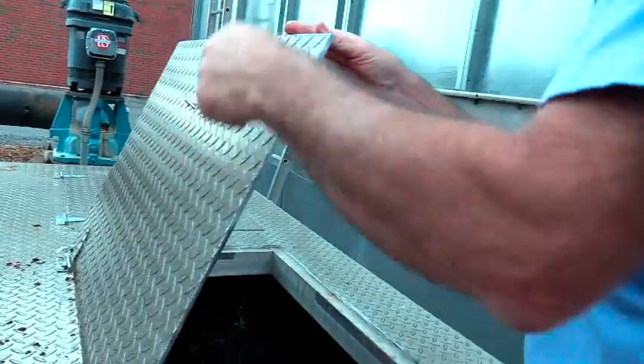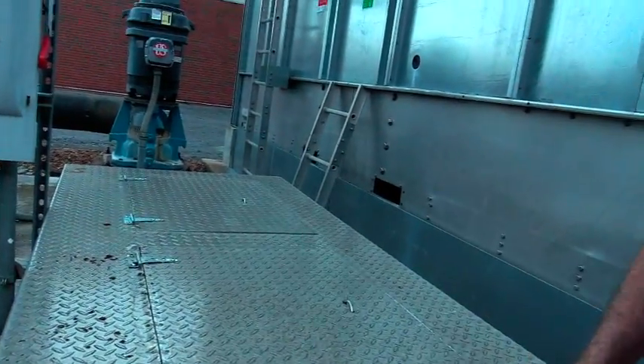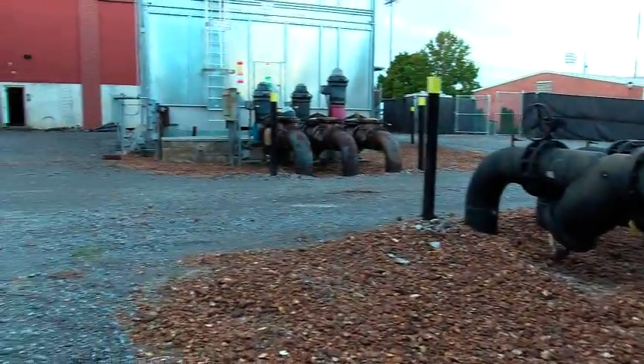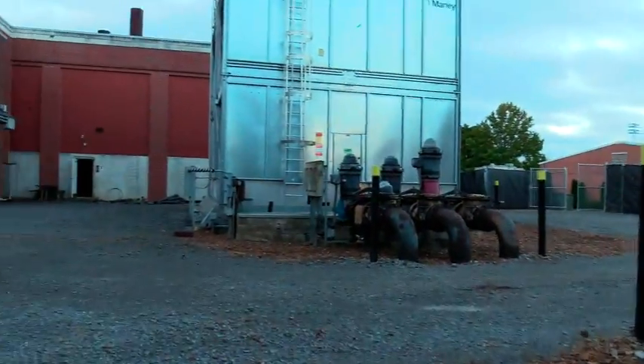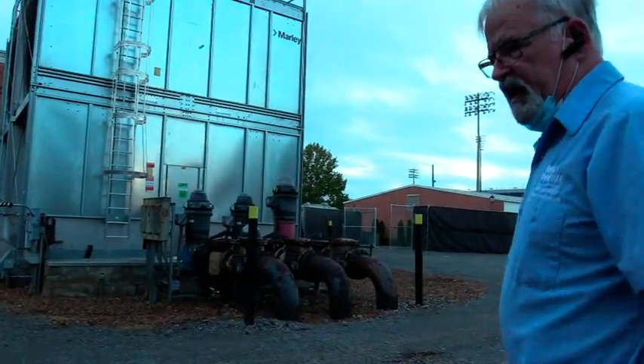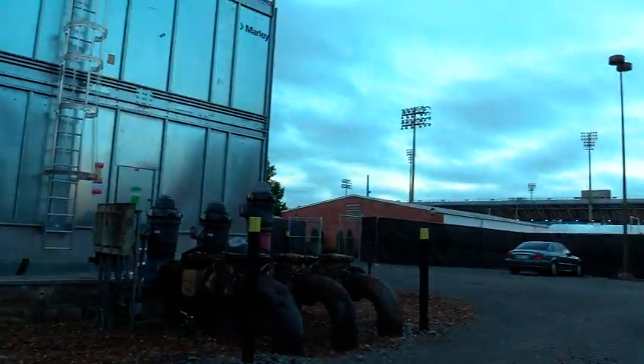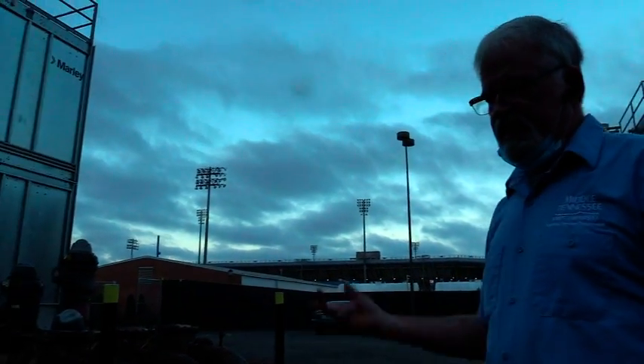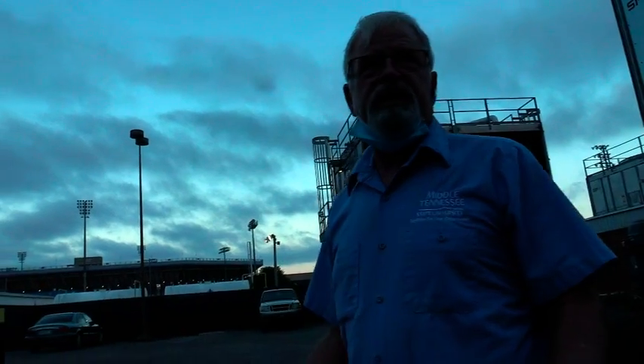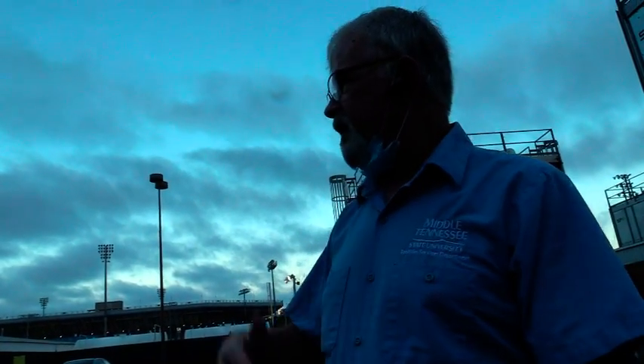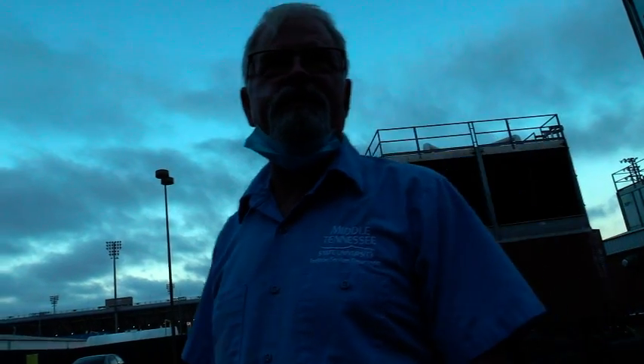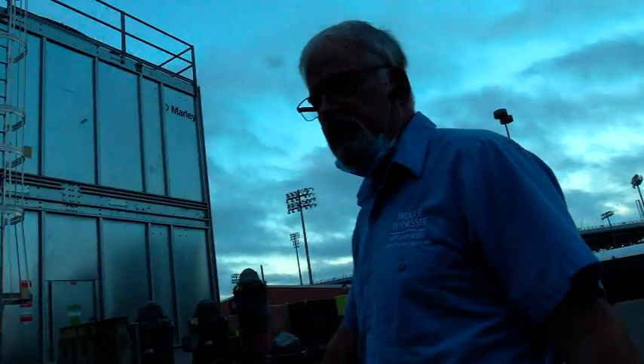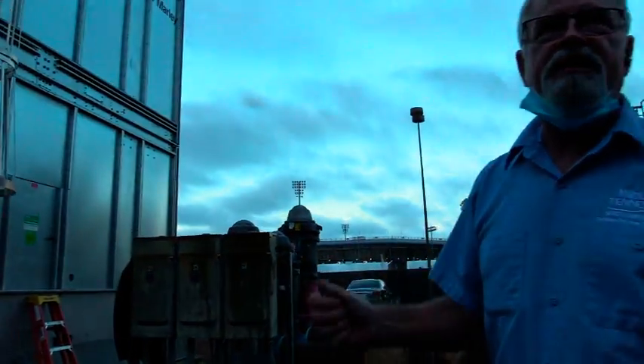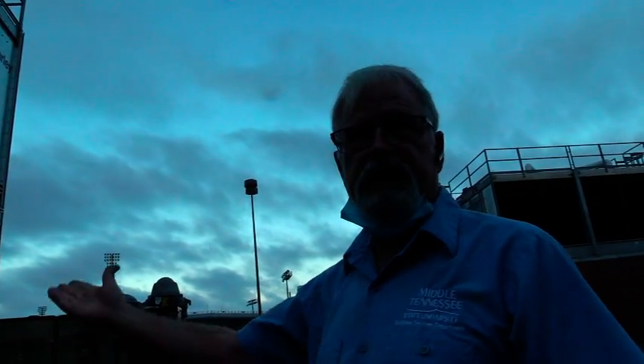So, I hadn't closed that out yet — Chris figured out what was going on with it. I had to come over and look at it one day, but I've got a spare one ordered, so we'll have one. These floats are easy to clean, stuff like that. This one was reading real bad and couldn't even move. I had SMR look at it, and I told Chris about it. Chris took it upon himself to look at it — he cleaned it up and got it working good. That's the reason I'm keeping that spare, which doesn't hurt to have. Because if that float goes out, you have to manually control it by hand, and that's risky — you'll either overflow it or get it too low, and that'll short your compressors.